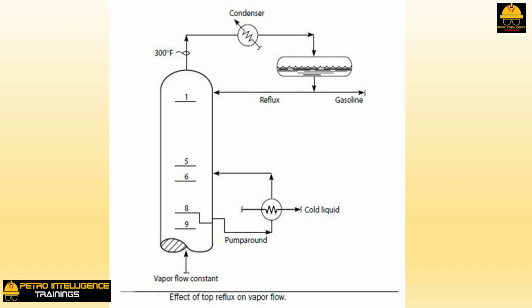As the molecular weight decreases, the volume of each pound of vapor increases. As the molecular weight of the vapor decreases, the density of the vapor decreases. As the density of a vapor is reduced, each pound of vapor occupies more volume. It is true that cooler vapors do occupy less volume per pound than do warmer vapors of the same composition. That is, gases and vapors tend to contract on cooling and expand on heating. However, this is a small effect compared to the increase in the volume of vapors, due to the decrease in the vapor's molecular weight.